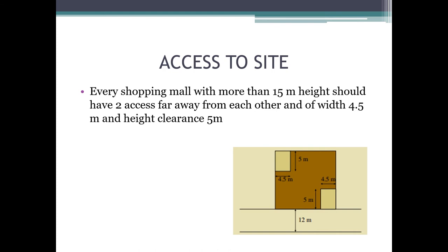Access to the site. Every shopping mall which is more than 15 meters in height should have two accesses far away from each other, with a width of at least 4.5 meters and a height clearance of 5 meters, because it provides safe approaches for the firefighters.